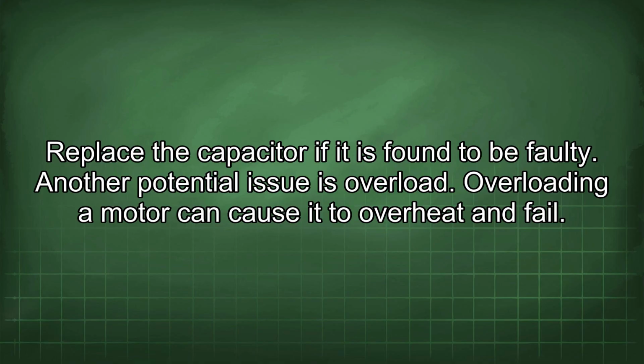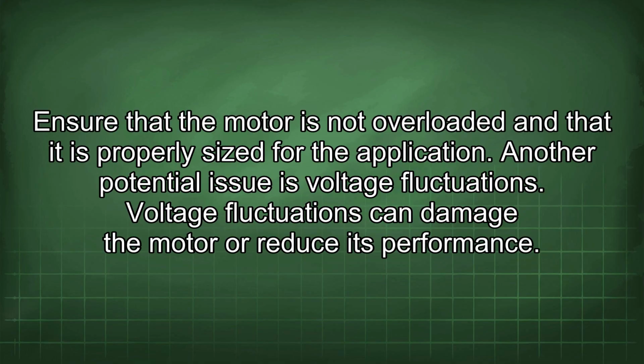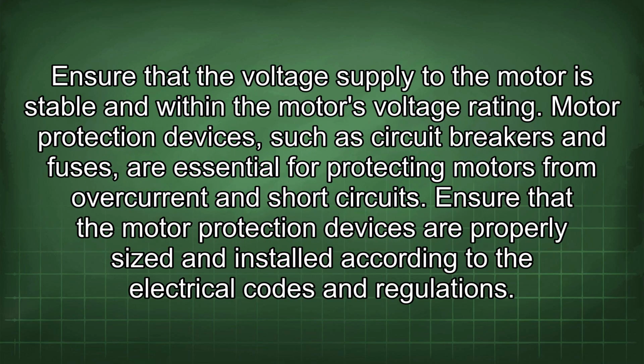Another potential issue is overload. Overloading a motor can cause it to overheat and fail. Ensure that the motor is not overloaded and that it is properly sized for the application. Another potential issue is voltage fluctuations. Voltage fluctuations can damage the motor or reduce its performance. Ensure that the voltage supply to the motor is stable and within the motor's voltage rating.